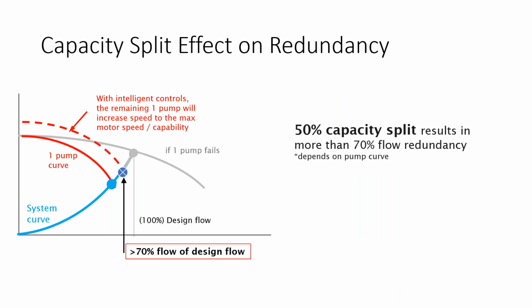So the engineering behind this is based on the capacity split effect on the redundancy. When you have intelligent controls, the single pump curve on a Tango will land us here on the system curve. At 100% design, you'll be all the way out here on the gray spot. But generally, we have an extra buffer of flow available from that pump if we speed it up a little, and we'll get 70% of the design flow out of a Tango if one of the motors fails. So instead of an actual 50% split, we'll have a 70% flow redundancy, and that's based obviously on the pump curve.